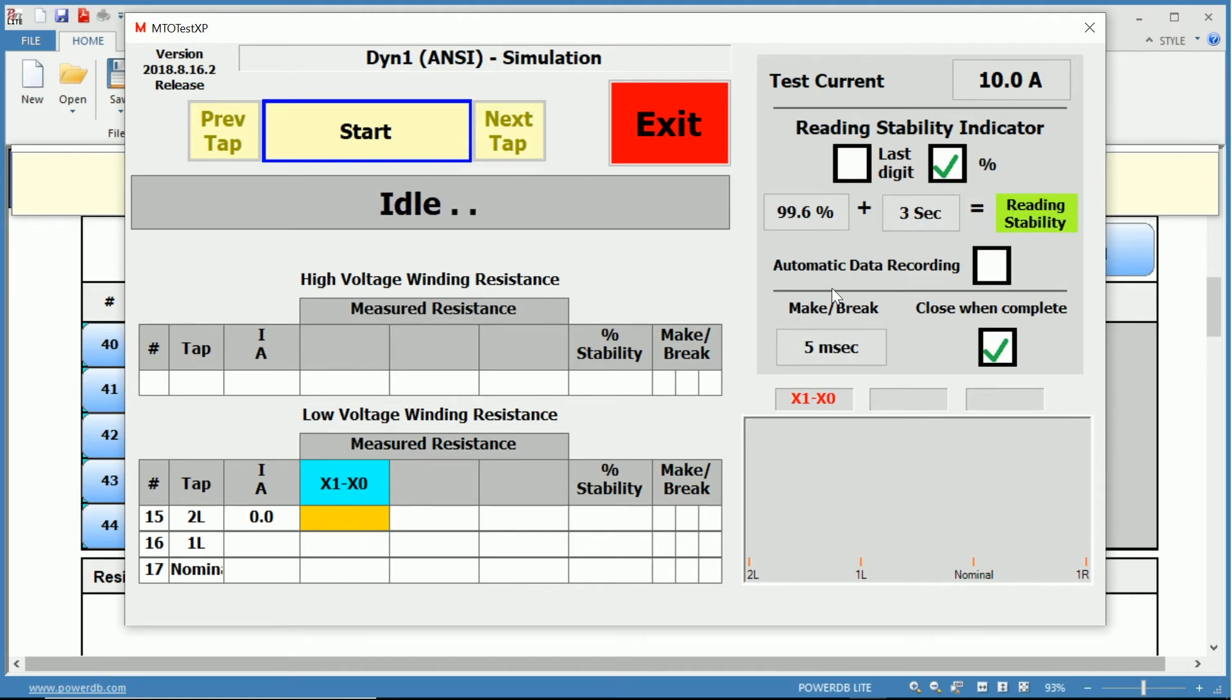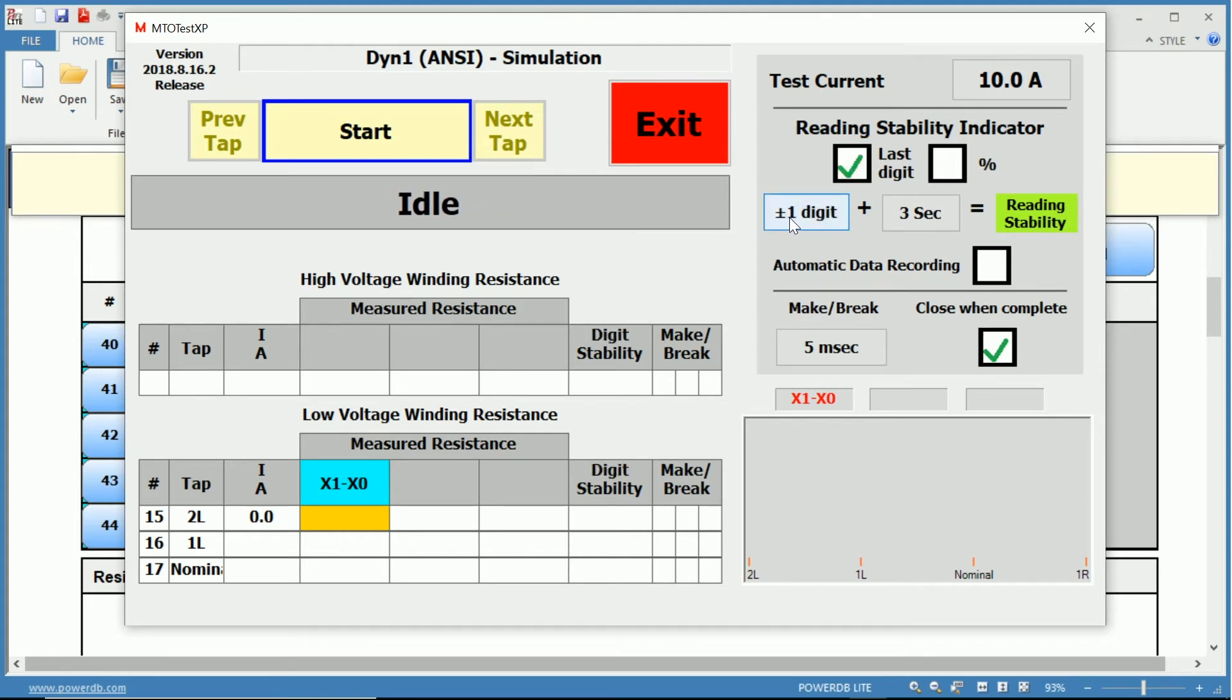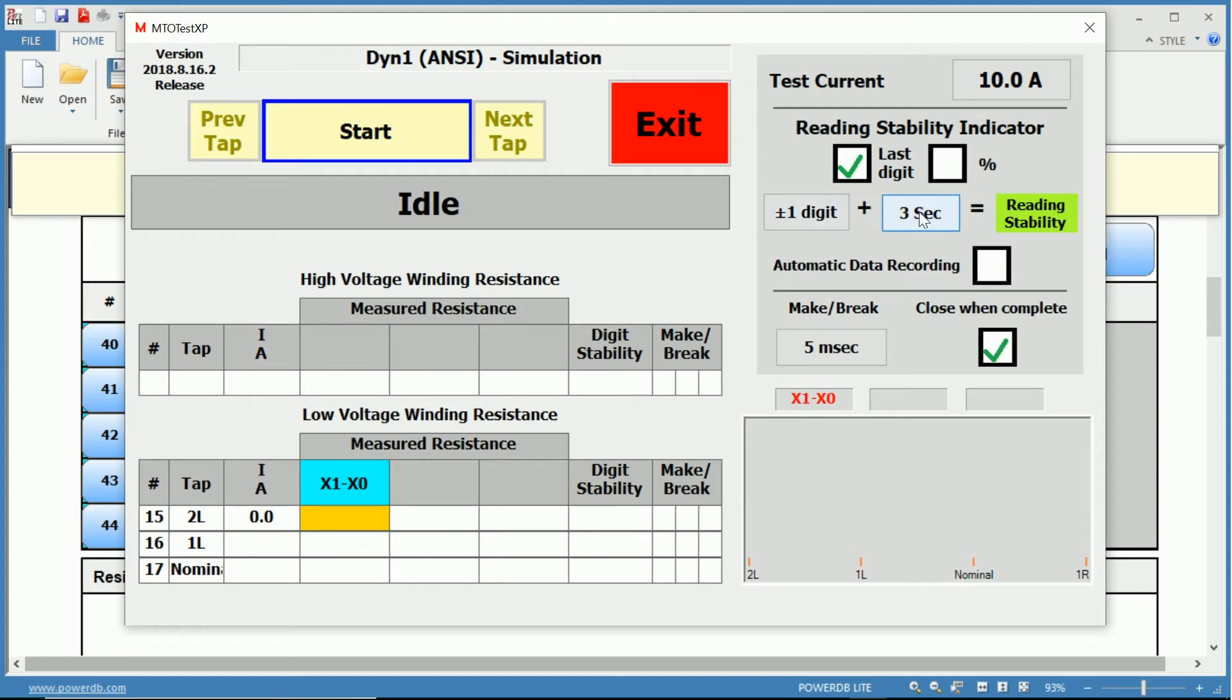So once the current is 99.6 percent stable for three seconds, that equals our stability, our reading stability, and then we take that measurement and it records down here in the table. We can also change this to last digit, in which it's plus or minus one of the final digit of your measurement.